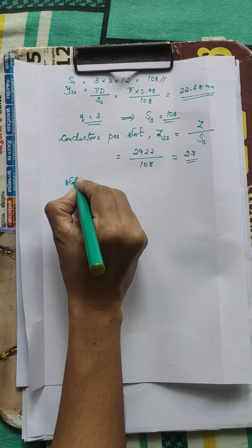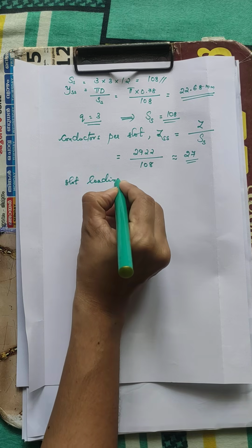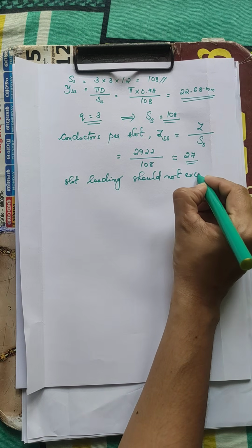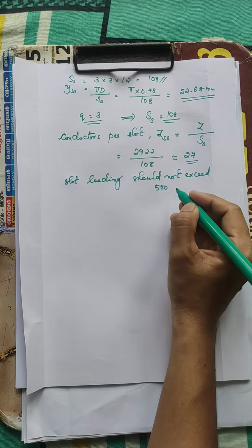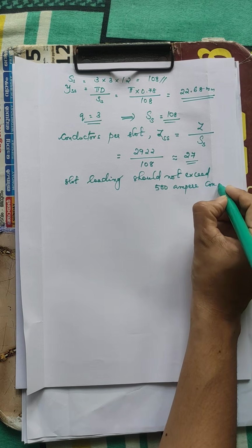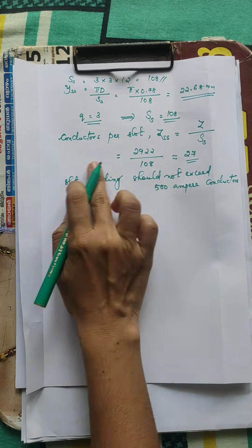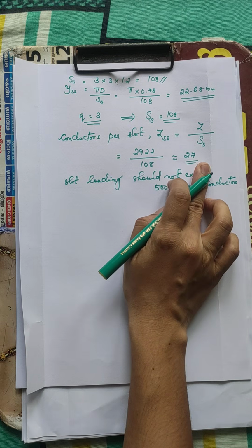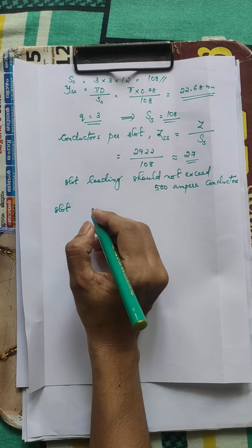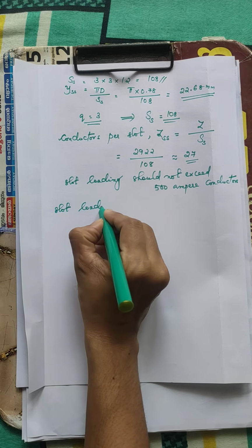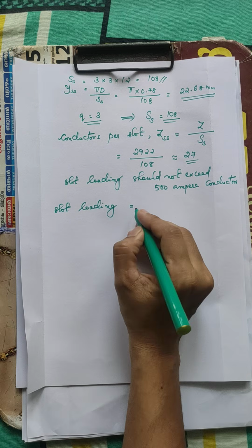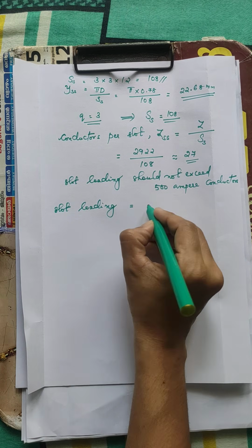That is, the slot loading should not exceed 500 ampere conductors. For this particular value of conductors per slot, we need to calculate the slot loading and check whether it is less than 500. Slot loading means how much a slot is electrically loaded.